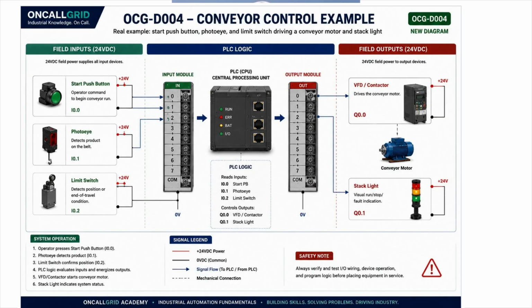A limit switch's roller arm can just snap, and sometimes the contact itself stops working, so it's worth checking whether it's wired as normally open or normally closed before you assume the switch itself is bad. On the output side, a contactor's contacts pit, a solenoid coil burns out, a stack light bulb or LED segment dies, and a VFD trips a fault or its cooling fan gives out. Honestly, knowing the common failure for each device is half of troubleshooting it.